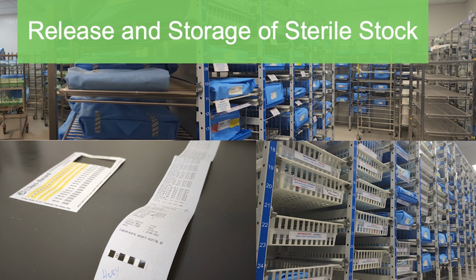Establishing a setting that reduces the chance of contamination after sterilization is emphasized in the AS/NZS 4187:2014 standard. To stop microbes from growing, sterilized objects should be kept in dry, clean, and well ventilated areas. Adequate shelving and storage options should be used to allow for simple retrieval while reducing the possibility of physical damage or crushing. It is crucial to regularly check storage rooms for cleanliness and protocol compliance.